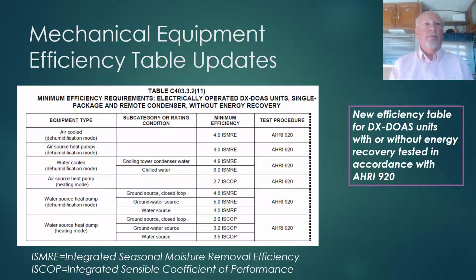If the primary purpose of your DOAS system is for dehumidification, then you would use the ISMRE rating, which is integrated seasonal moisture removal efficiency. So the higher the rating, the more efficient it is at removing moisture. If you are using a heat pump coil operating in the heating mode, and so you're tempering outside air coming into the unit before being delivered to the space, then we use the integrated sensible coefficient of performance value. So those are the minimum efficiency values per AHRI 920 for that rated equipment.